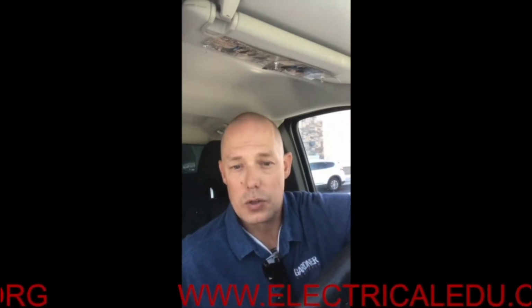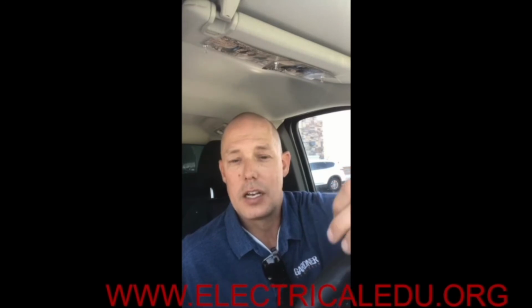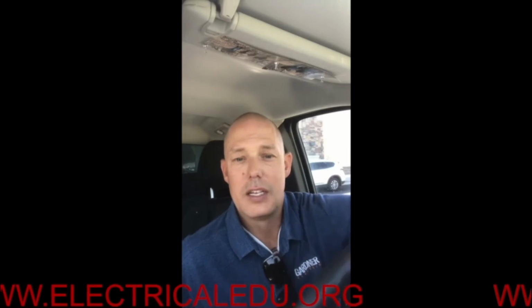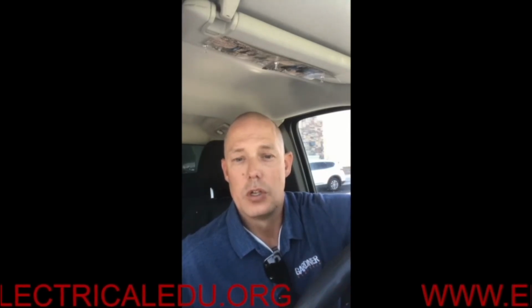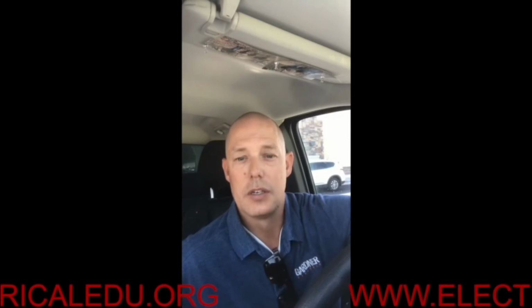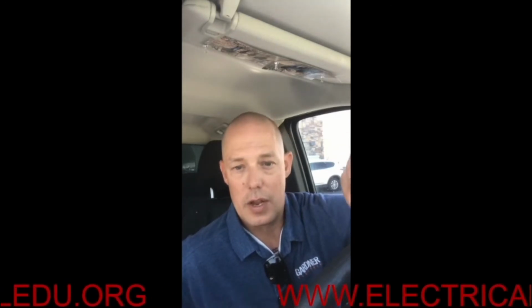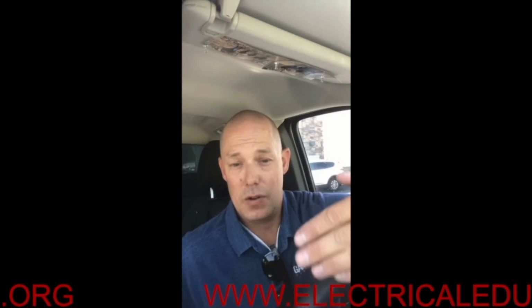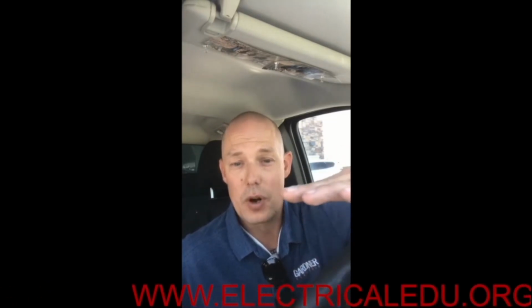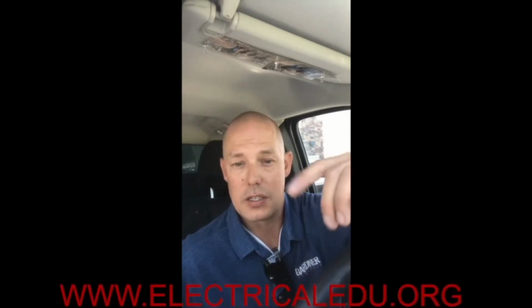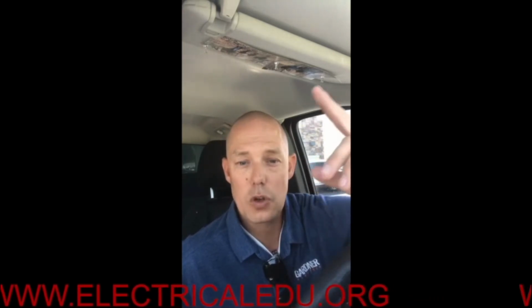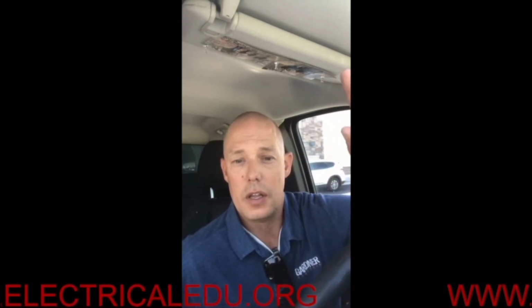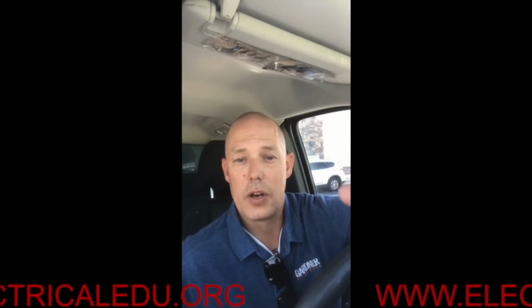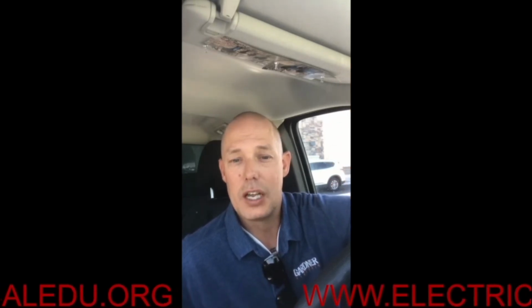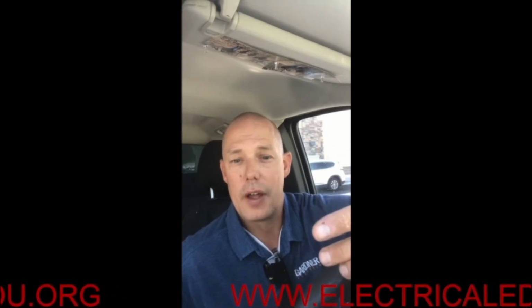Now, also in that same section, that is for an unknown. But we know that the terminal ratings on all HVAC equipment are rated for the 75-degree column. So don't get lost in 110.14(C), where it tells you 100 amps or less is 60. And that doesn't get important until you get into the 50 amp range. It starts changing the wire sizes according to the different temperatures. So we're going to size this off of the 75-degree column on 30 amps, which is going to give you a number 10 on a 45 amp breaker.